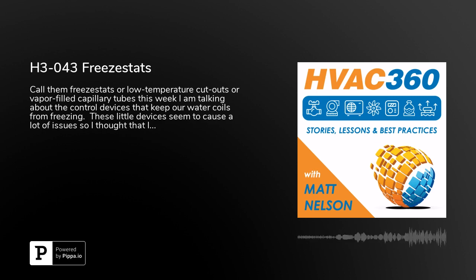If the freezestat trips off, so what? You can get freezestats that are bypassed, not used, held open, rewired, taken out, or disconnected, and then you're back to no protection for the water coils that are in the unit. So you want to make sure they're tested correctly and installed correctly, so you can avoid the nuisance trips and things like that.